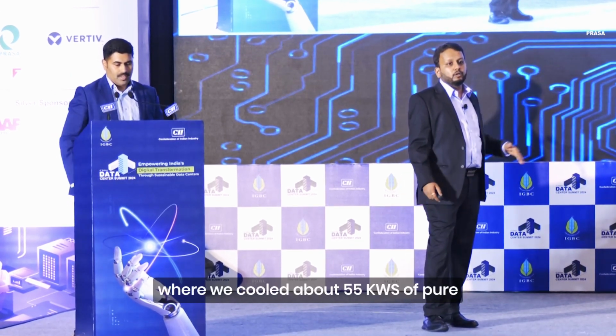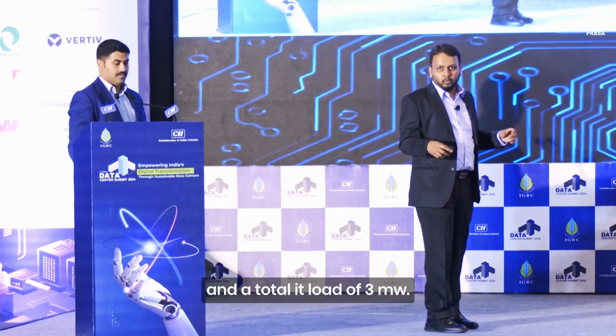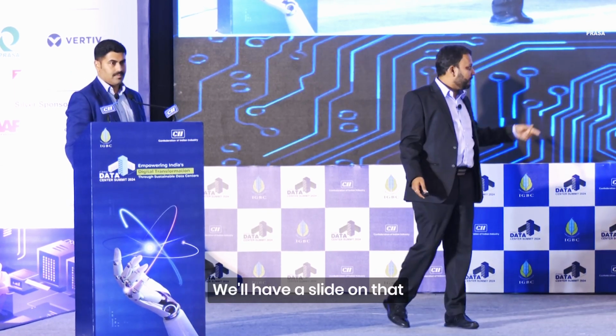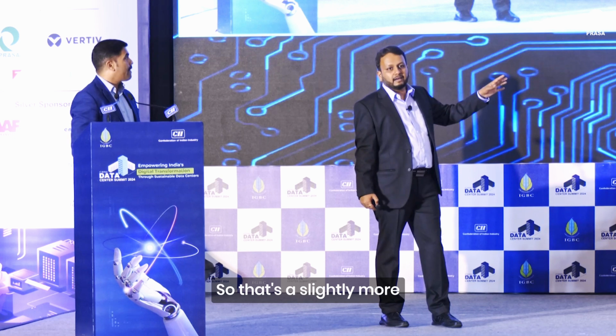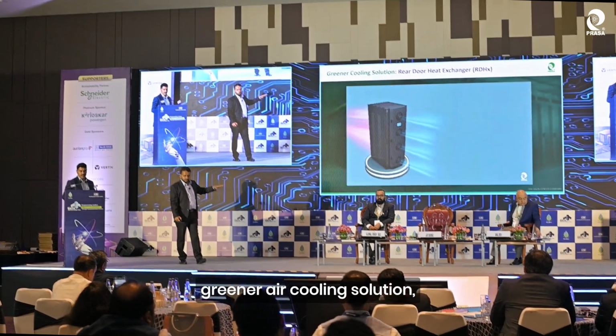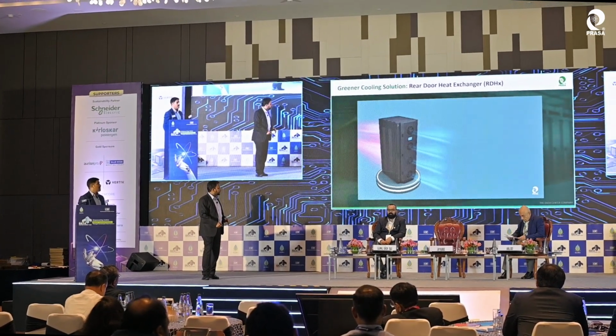We've been fortunate to participate in and implement a project where we cooled about 55 kilowatts of pure HPC inside one rack, with a total IT load of 3 megawatts. We'll have a slide on that further as well. So that's a slightly greener air cooling solution, as I may call it.